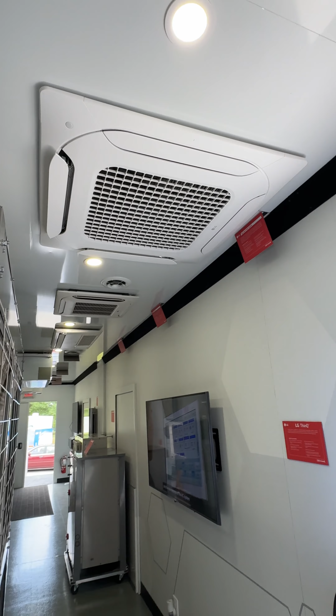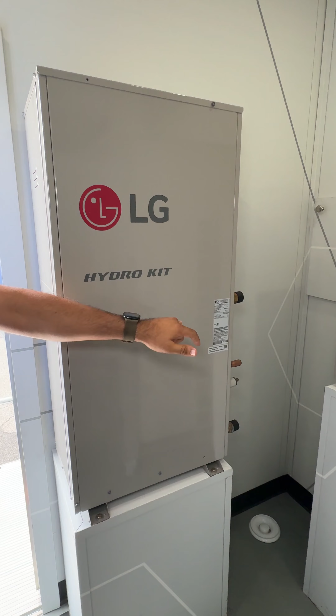These same units are going to be changed to R32, which is going to be multi-V I. Right now it's still 410A. You get another year of 410. It's going to be changed. And they hook up to all these indoor units, and they hook up to these hydro kits also, which are the new products, so you can heat your water. You can heat your water to 170. You can heat and cool your water to 140 and 40 degrees.